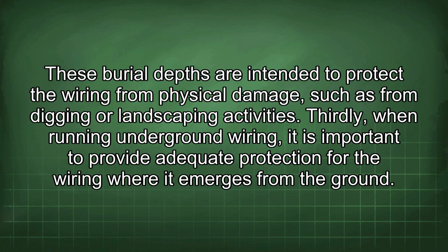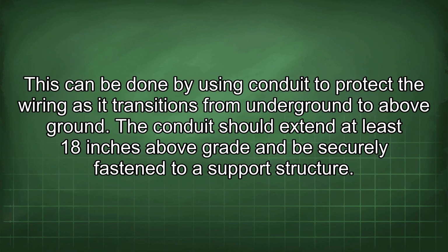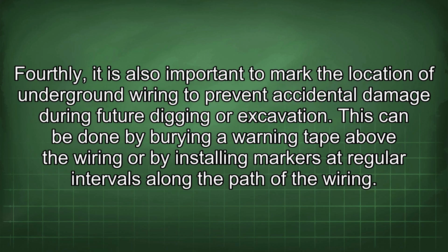Thirdly, when running underground wiring, it is important to provide adequate protection for the wiring where it emerges from the ground. This can be done by using conduit to protect the wiring as it transitions from underground to above ground. The conduit should extend at least 18 inches above grade and be securely fastened to a support structure. Fourthly, it is also important to mark the location of underground wiring to prevent accidental damage during future digging or excavation. This can be done by burying a warning tape above the wiring or by installing markers at regular intervals along the path of the wiring.